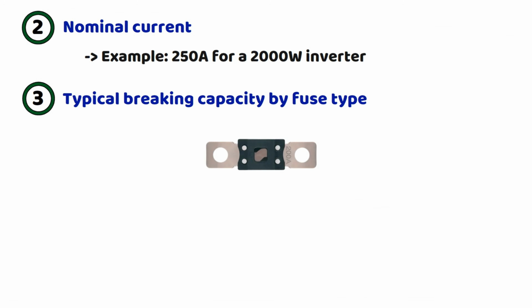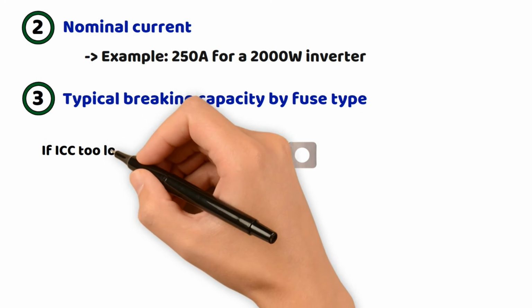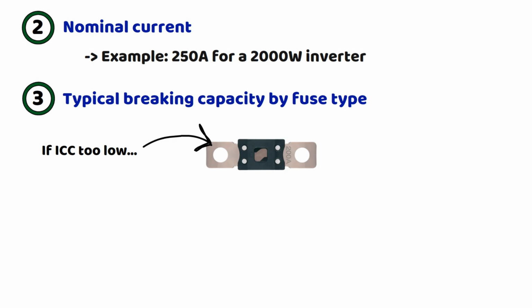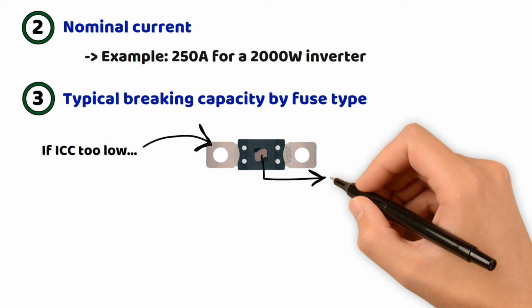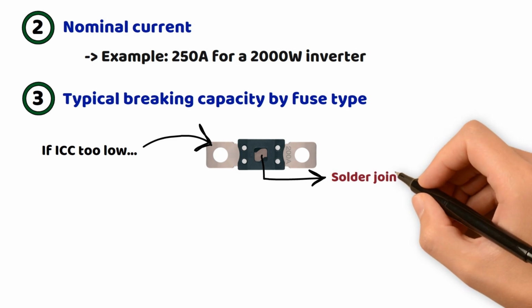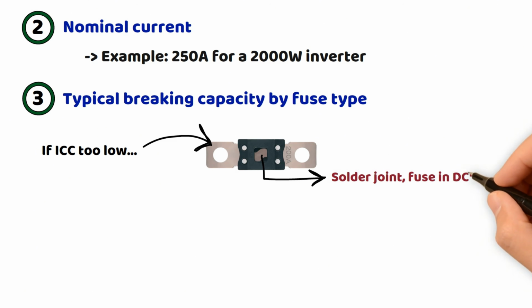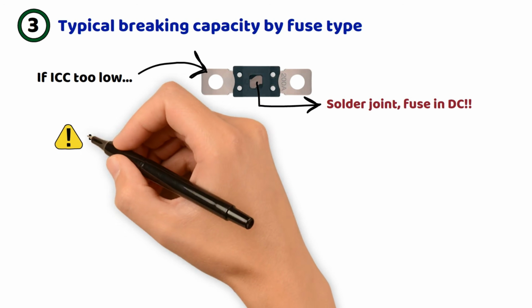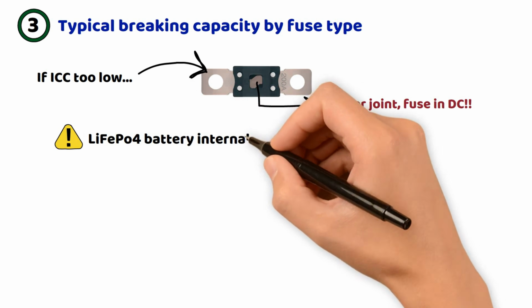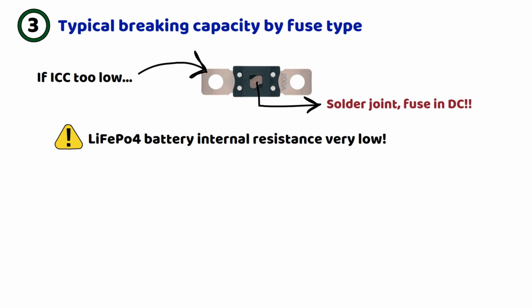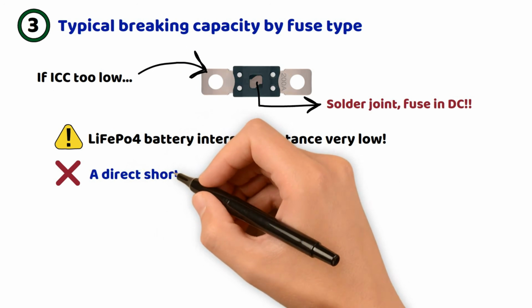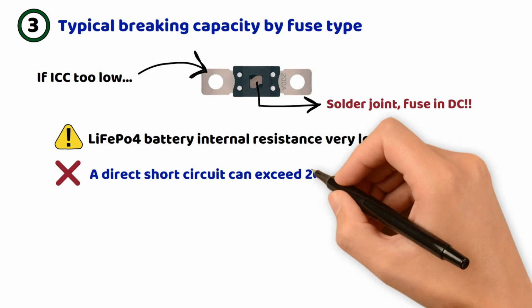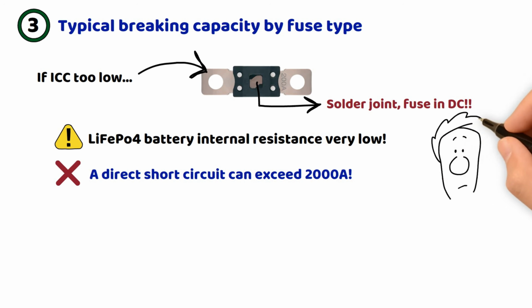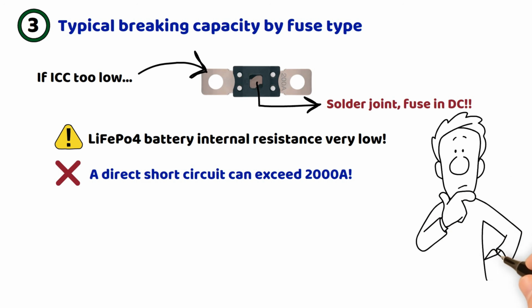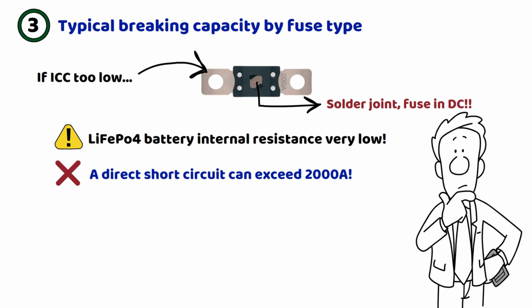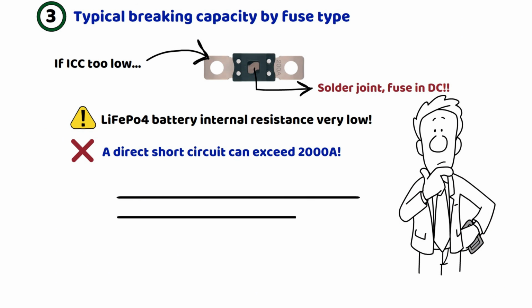This is the fuse's ability to instantly stop a massive current during a short circuit. Lithium batteries can release thousands of amps in a fraction of a second. If the fuse's breaking capacity is too low, it can literally turn into a welding rod and continue to let current pass even after it has melted, causing a fire. You might be wondering why. Well, it's because the internal resistance of a lithium battery is very low, as we already discussed in a previous video about car alternators and lithium batteries. The short circuit current is calculated by dividing the voltage by the internal resistance of the battery, and it can easily reach over 2000 amps. Moreover, the BMS cutoff might not be as responsive, even though it remains a safety protection to take into account. However, choosing the right fuse will definitely protect you from a fire.